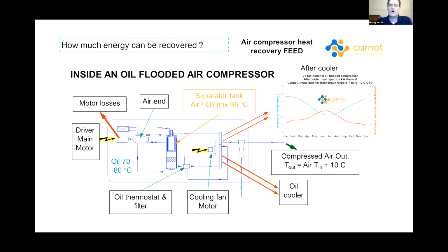So you can't overcool the system, or else you'll get water build-up and you'll rust out inside your machine. If you go too hot, the oil will break down very quickly, and you can actually get separator fires and fires inside a compressor. So it's a bit of a balancing act. The compressor controls will shut down a machine. If it gets much above 95 degrees, it will start to alarm, and they'll shut down between 100 and 105. That depends upon the compressor manufacturer.